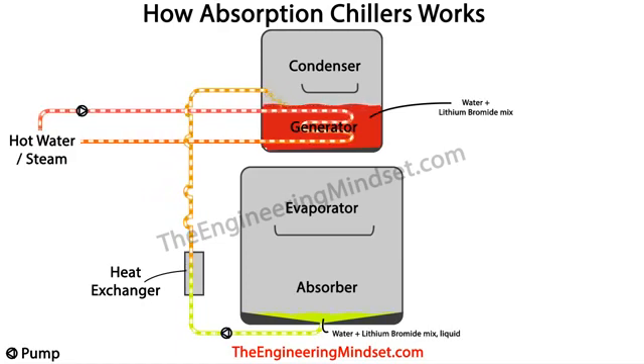Next, heat is added to the reservoir containing the lithium bromide and water, and this will begin the separation process that we saw earlier. Now this heat is usually in the form of waste heat and will typically come from hot water or steam that's being pushed around a heat exchanger of tubes inside the generator.